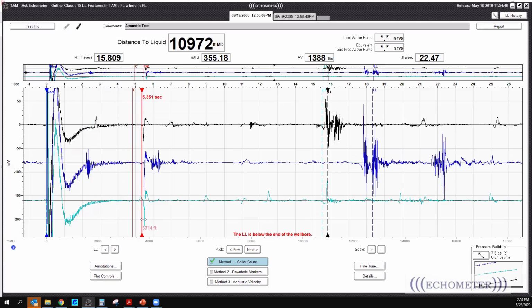Well, wait, I find here something very common. This down kick at 5.4 seconds. So there are more kicks here. It's not being repeated. And if I have a fluid level kick at 5.4, I might find that trace at double time, which is 10.8, right here.